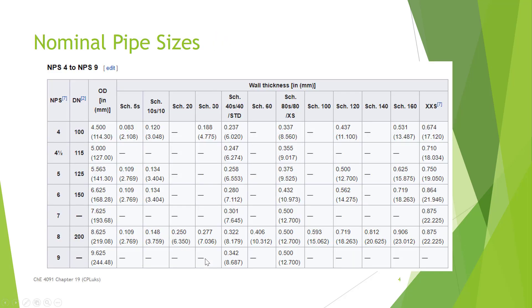You're probably familiar with this, but just in case — we have things called nominal pipe sizes. This is the mid-range for industrial purposes: four, five, six inch pipe, four and a half inch. Not every possible size is available. For example, a four inch nominal pipe has a four and a half inch outer diameter, and with a schedule 40 wall thickness of 0.237 inches, the inner diameter is actually a little more than four inches. So there isn't any particular measurement that is exactly the four inch nominal — we just call them by these nominal sizes because they're close, and all of industry manufactures to these sizes.